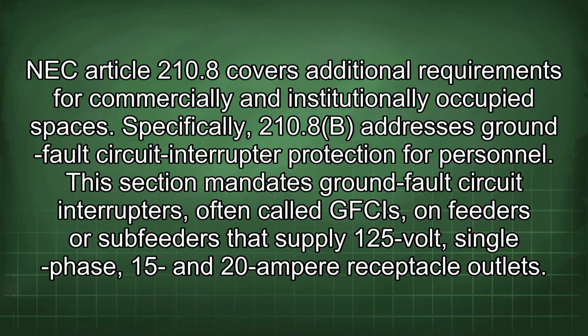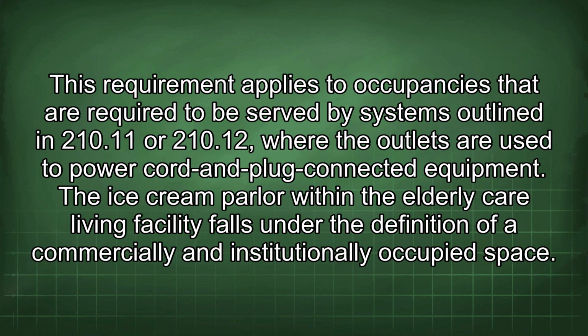NEC Article 210.8 covers additional requirements for commercially and institutionally occupied spaces. Specifically, 210.8b addresses ground fault circuit interrupter protection for personnel. This section mandates ground fault circuit interrupters, often called GFCIs, on feeders or subfeeders that supply 125-volt single-phase, 15 and 20 ampere receptacle outlets. This requirement applies to occupancies that are required to be served by systems outlined in 210.11 or 210.12, where the outlets are used to power cord and plug connected equipment.